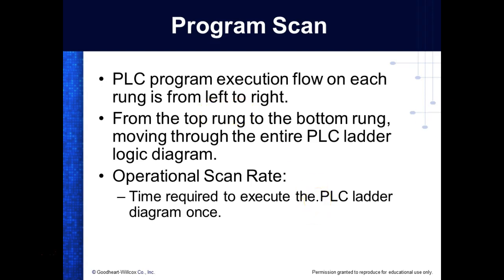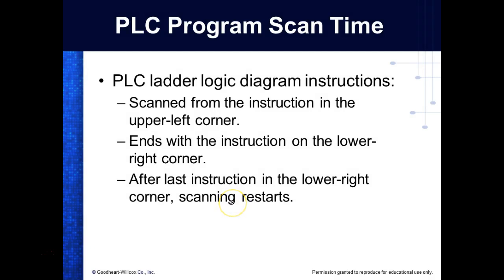And we can look at the scan time. In fact, I'll show y'all in the program manual for the 1100. It gives you the time every instruction takes. So if you wanted to figure out how long it took to scan the rung, you would just come in and add all those things together, and that would tell you how long it did if you needed to. We're not going to worry about that in this class. It scans from the upper left-hand corner, starts at the left, goes right, and works down.